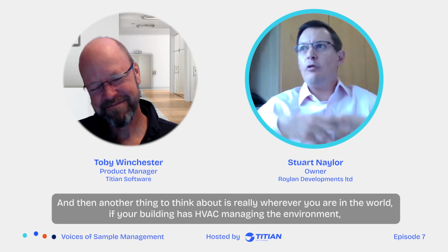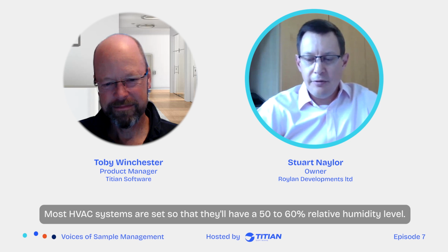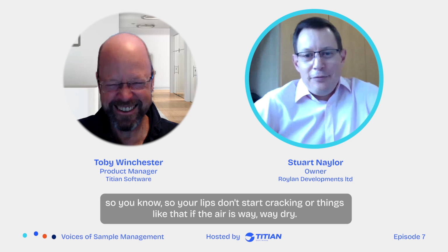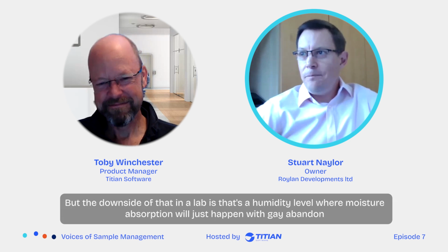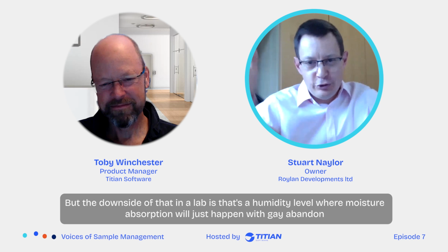Yes. Another thing to think about is, wherever you are in the world, if your building has HVAC managing the environment, so that's full environmental control, most HVAC systems are set so that they'll have a 50 to 60% relative humidity level. That's for human comfort, so your lips don't start cracking if the air is way, way dry. But the downside of that in a lab is that's a humidity level where moisture absorption will just happen with gay abandon. So they're almost pumping in moisture, in a modern building, literally. Yes, there's a thought for people designing labs in the future.